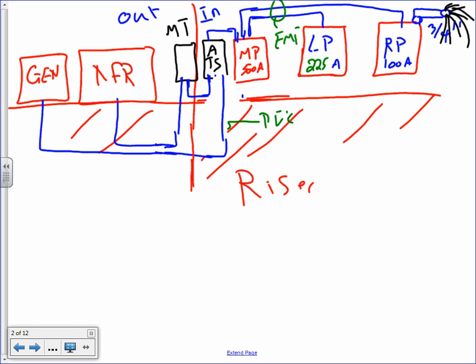So that's the meter. So these are underground. Anything underground, guys, will be underground. So this is PVC, and these are PVC. Okay. Any question, guys? So I have a transformer. I went into the termination meter terminals, or termination box. Out of the termination box, I got into the building, the auto transfer switch. Out of the auto transfer switch, I fed my 500 amp panel, and I fed the two receptacle and lighting panels from it. And then I have a generator that I went directly into the auto transfer switch, because the generator is going to flip between both of them. So that's basically what you're going to have tomorrow when you build your system. Did you guys modify this one slightly to look something similar to this? Yes, no?